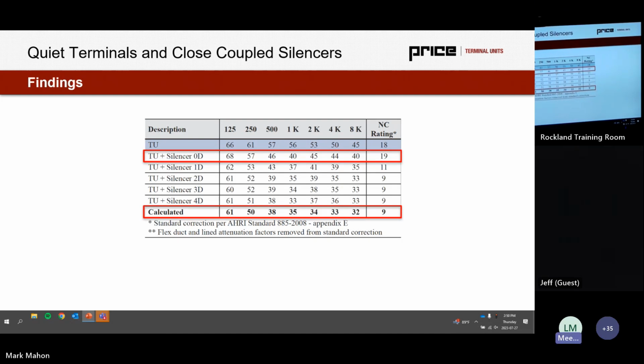The thought process is turbulent air and localized velocity hits the nosing of the silencer and it generates more sound than it dissipates. I've seen this on an actual project in New York. We were basis of design on that project. A contractor pitched a standalone silencer and a terminal from another manufacturer. They put them directly on the units. The space was very loud. We showed up to the job site. There was a terminal and silencer graveyard in the parking lot.